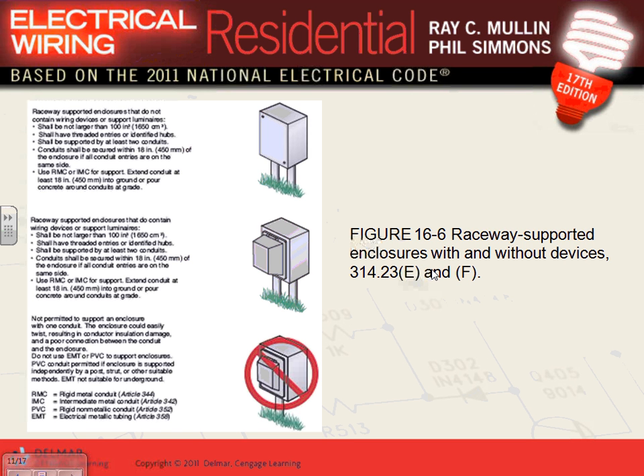So to avoid doing this, Chris, what do you do? You put this box against the wall, the outdoor wall, or you build a structure to support it if you don't want to use rigid or intermediate. PVC also, PVC Schedule 80 will get you there. Good support. PVC Schedule 80 will get you to support these 2 conduits coming from the bottom.